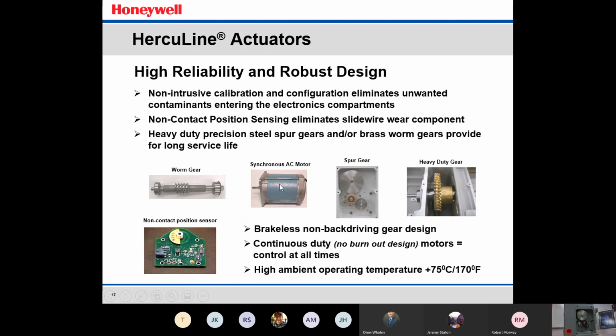The synchronous motor, AC motor, is what's used to drive both of these actuators. And if you look to the right here, there is a spur gear. This would be on the 10260. On the 10260, there's a little door that I'm going to show you in a little bit on the side that has 6 screws. And if you take that little door off, you will have the main gear, which is hooked up to the motor. You have a spur gear right here that is the fine mesh gear. And then you'll have a steel gear here that's connected right to the output shaft. This fine mesh gear here in the middle is called the breakaway gear. So as I mentioned earlier on, if you get into 2 times the rated stall torque, this gear will actually break before it damages the AC motor that's on the actuator. So as I said, this stall gear here is about 15, 20 bucks, and it's very easy to replace as well.